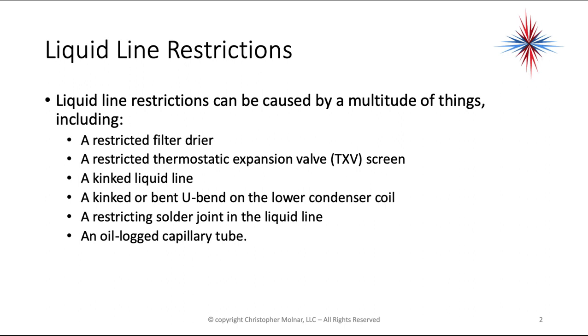A kinked liquid line is normally very easy to find — for example, someone hit it with a lawnmower. A kinked or bent U-bend at the lower condenser coil is also visual. A restricted solder joint in the liquid line may occur if someone used too much braze during assembly, or forgot to remove shipping caps. This should have been found at system startup, but look for temperature differences. A restricted solder joint will very often show up as frost on the liquid line because it's actually metering.